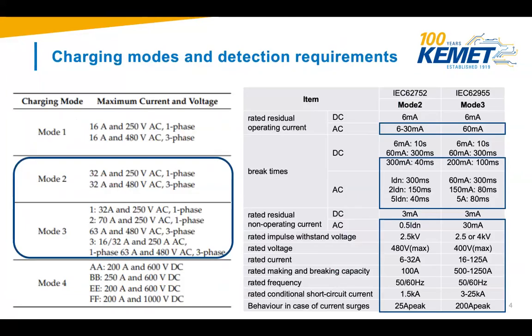When it comes to the requirements of these different charging modes and the leakage detection requirements, you can see some differences but also similarities. If we look at the different modes in the table, IEC 62752, which is mode 2, the DC level where leakage needs to be detected is in both cases 6 milliamps, but the AC level is different. Also the break times vary, but in general it's the same concept.